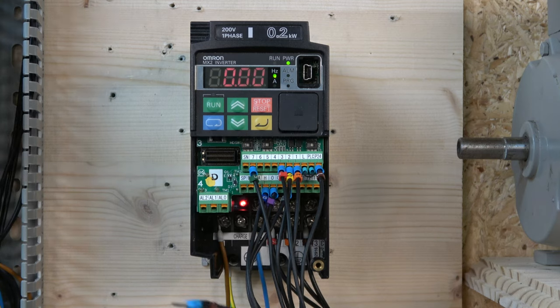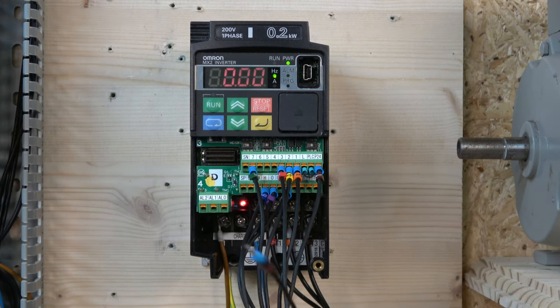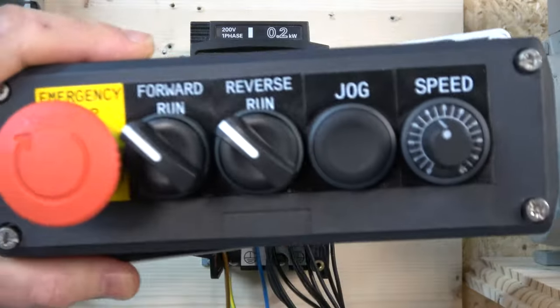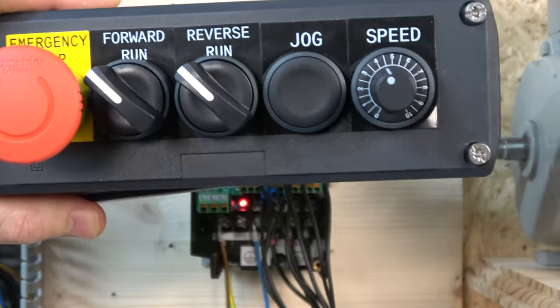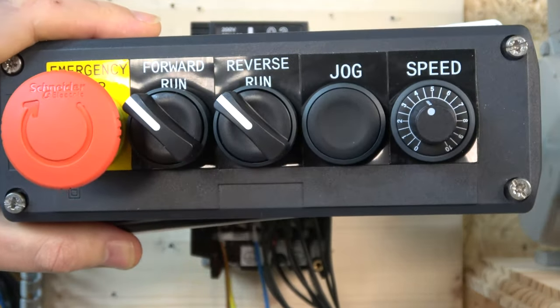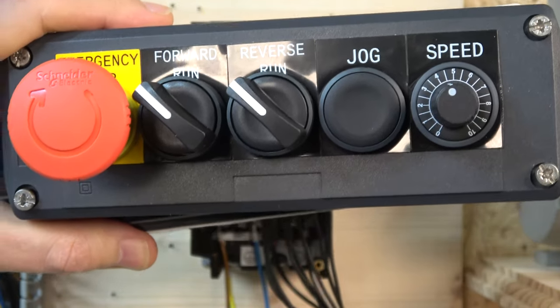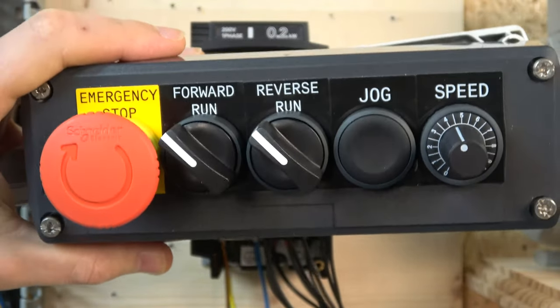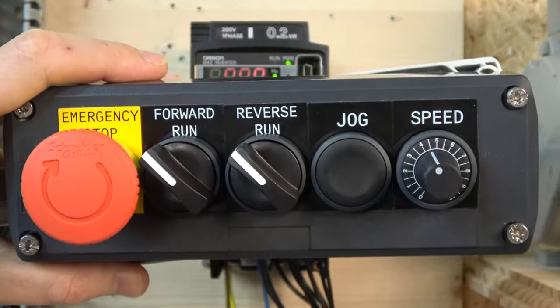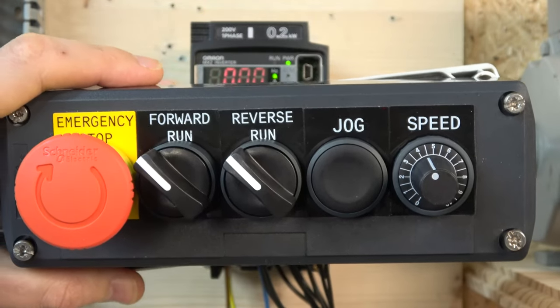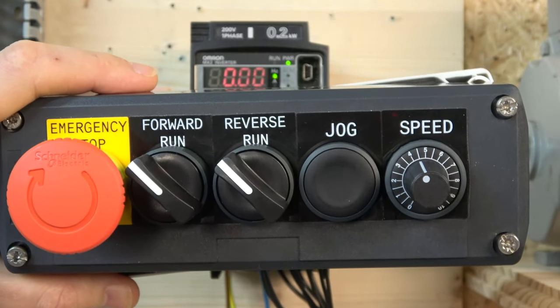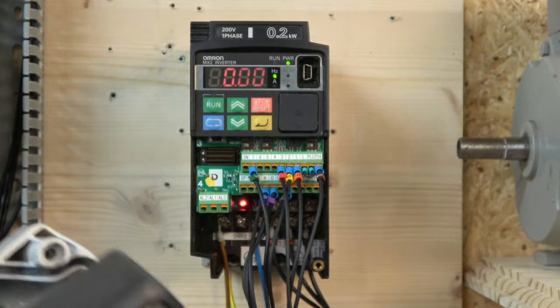The first station is going to look like this, which I usually do for a very standard two-wire control station which starts with a forward run, run reverse, jog and a speed, and also we will have an e-stop that will trip out the drive. It's going to come in as external trip and I'll show you in a minute how that is done.